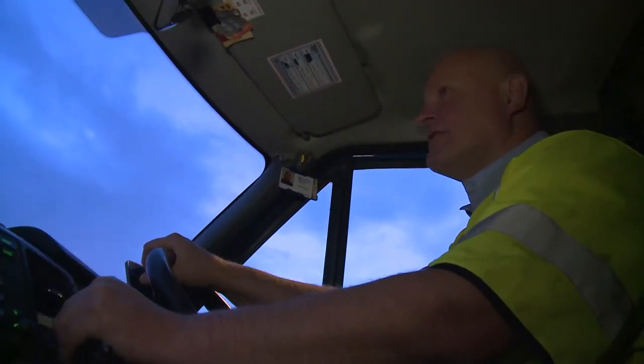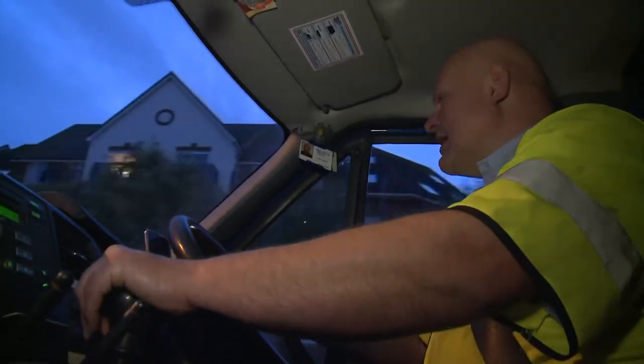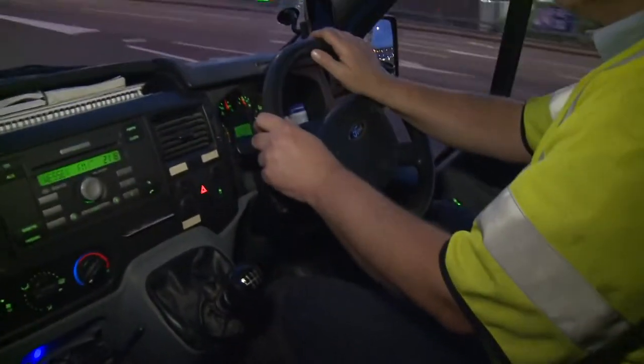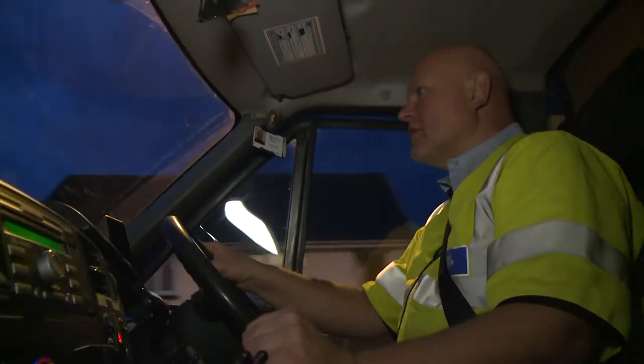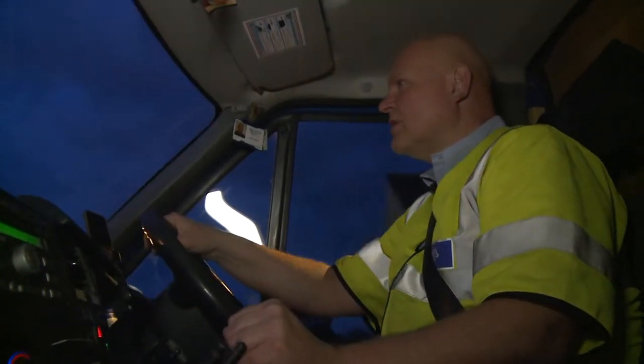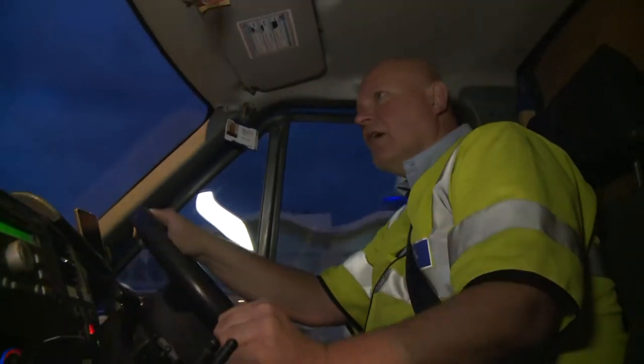The sun's finally set on sunny Weymouth. Your best leaks are found at night, because there's less usage, more pressure in the mains and less people about — there's less noise on the ground. Every little bit of help from our customers is greatly appreciated. If they spot any water running down the road, whether they think it's insignificant or not, please don't hesitate to give us a call or look on our website.